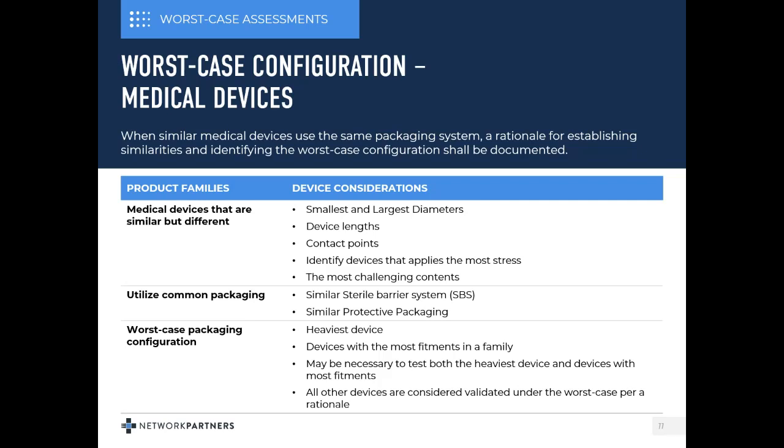So you pick the worst case, most challenging one. And again, this goes back to your resource load, is you don't have to test everything and spend hundreds of thousands of dollars to do this, providing you have the appropriate assessment documented.